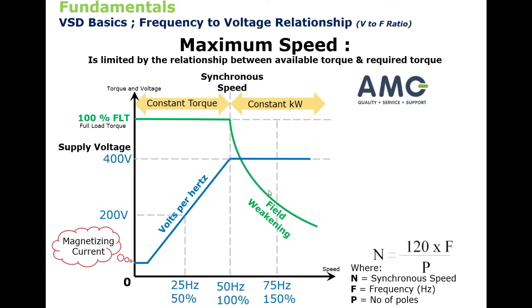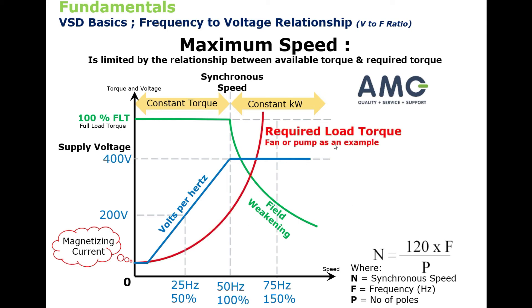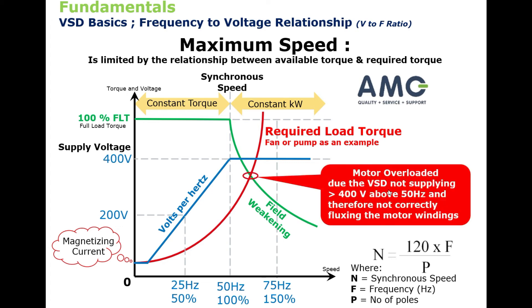The field begins to weaken, and if we apply a load such as a pump or a fan, where these two lines cross over is where the rotor will start to get behind the stator windings or the rotating field, and there will be more slip, therefore more current drawn, and the motor will overload.